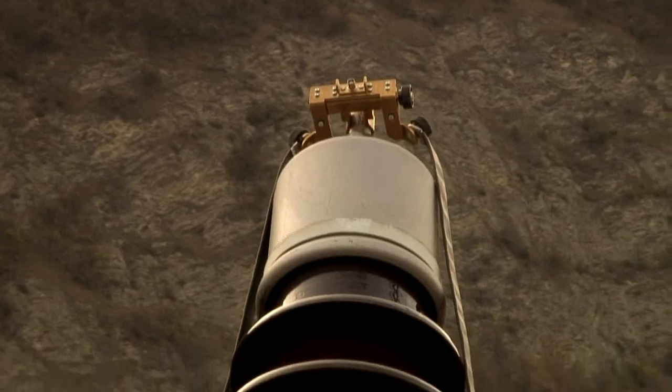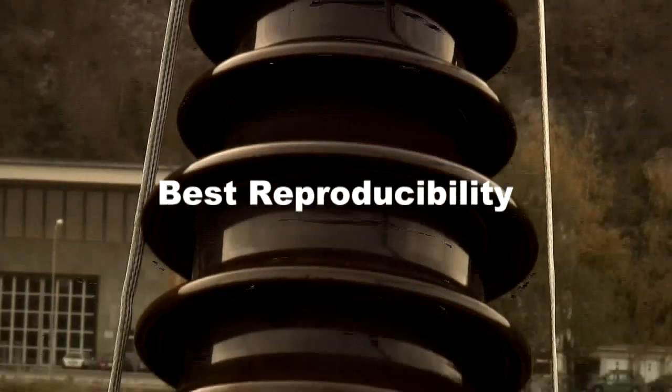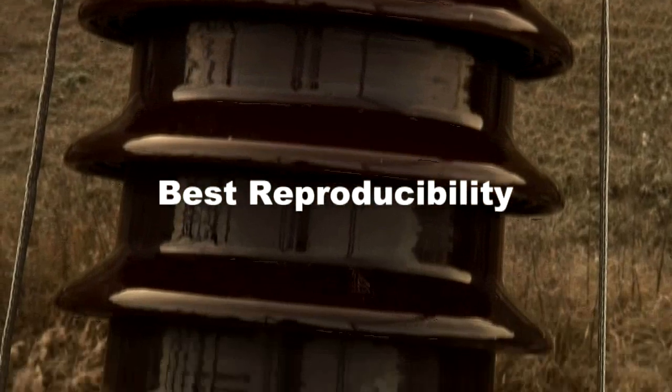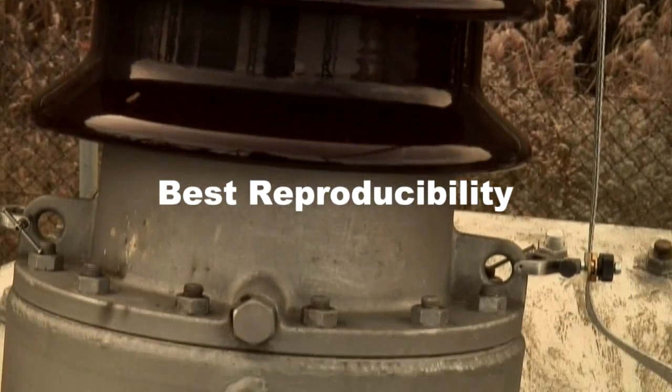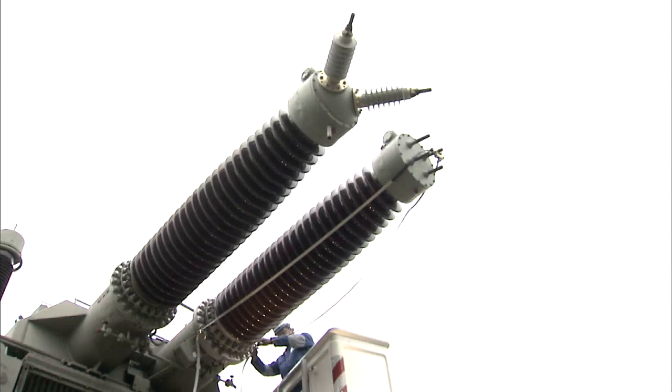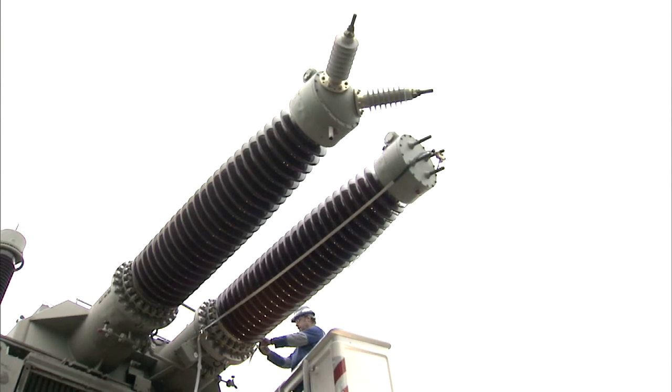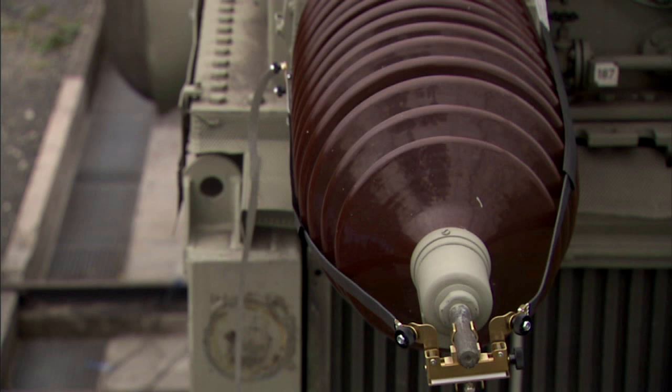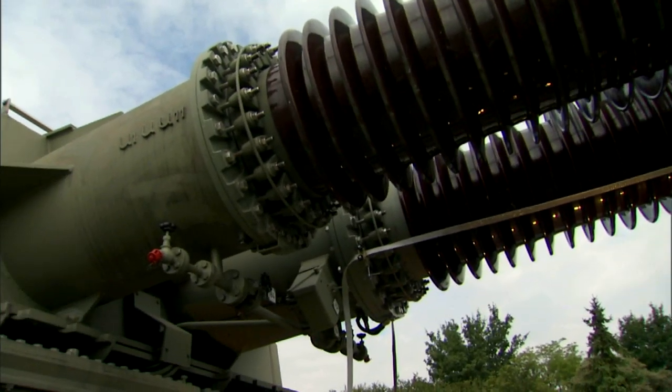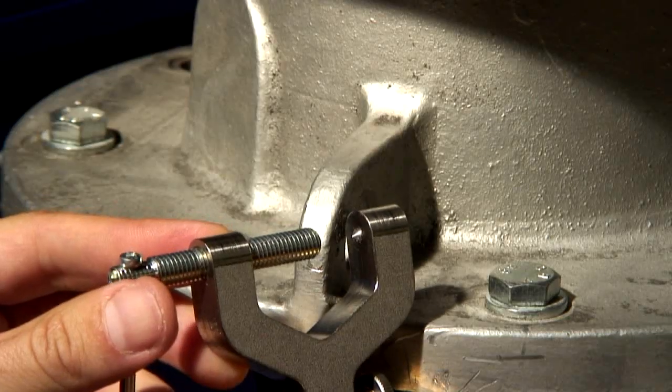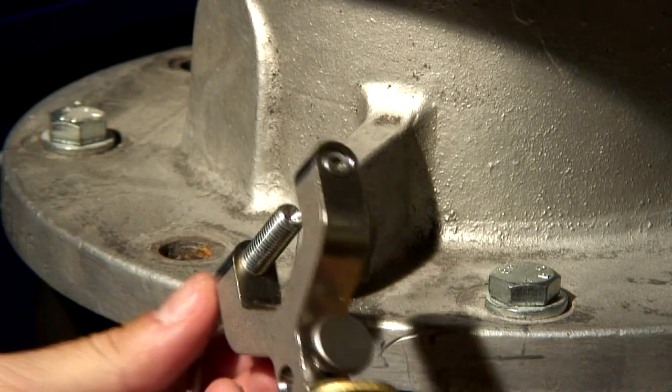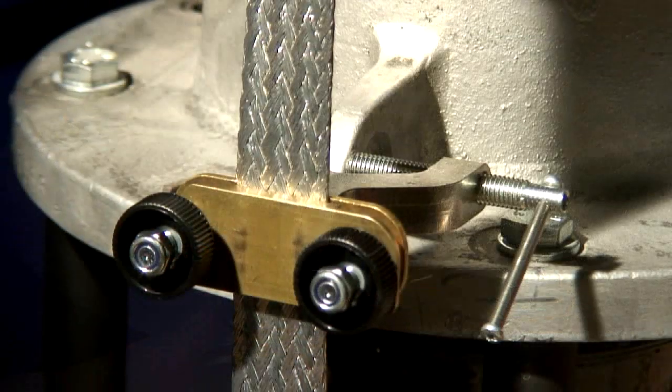Connection technique is critical to obtain precise and reliable results. The benefits of the Omicron method using clamped down braids include minimal pickup of interference signals due to connection close to the bushing, cancelling out of interference signals due to the use of two braided cables, minimal influence from the connection itself by using broad braids, and a high level of reproducibility due to a tight connection made using clamps and screws.